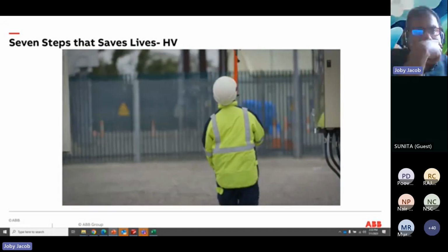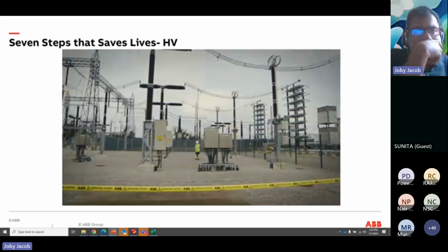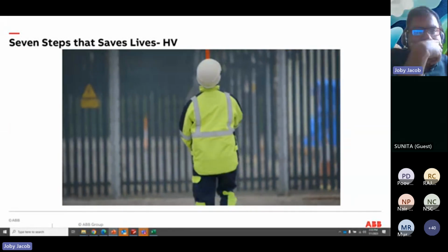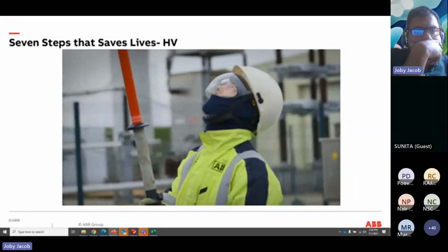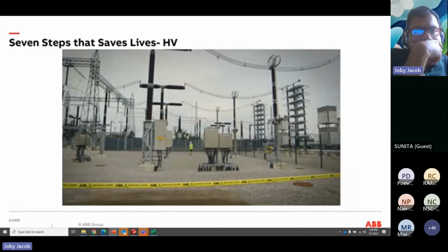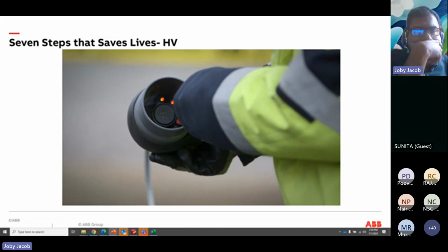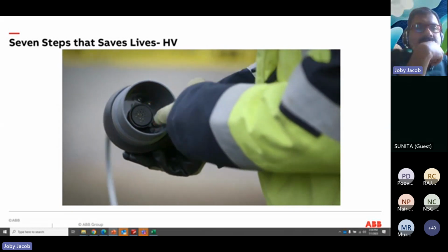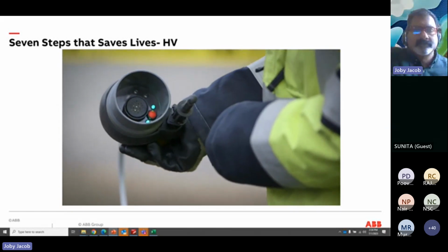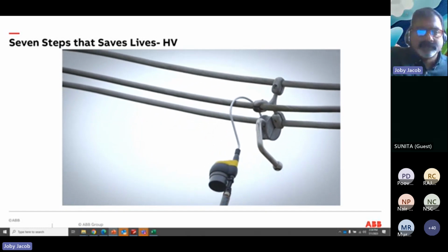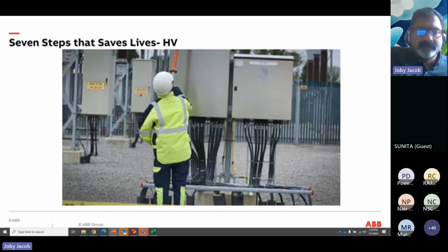Ensure to test for loss of voltage on all 3 phases where 3-phase applies. Finally, test the voltage detection device once again to ensure it is still working properly. This 3-step method is required without exception.